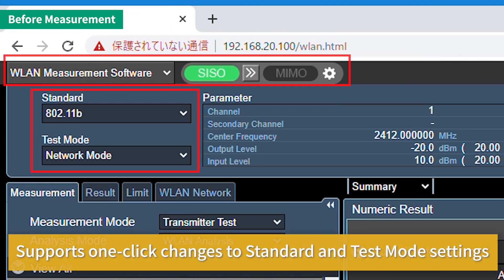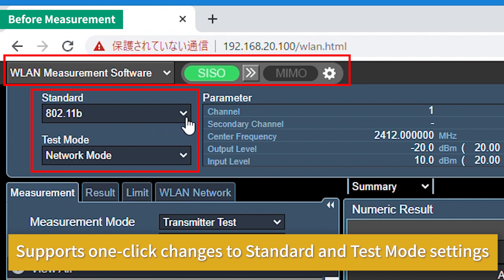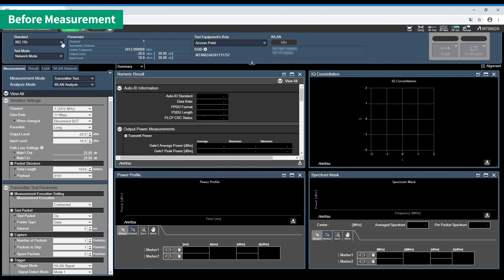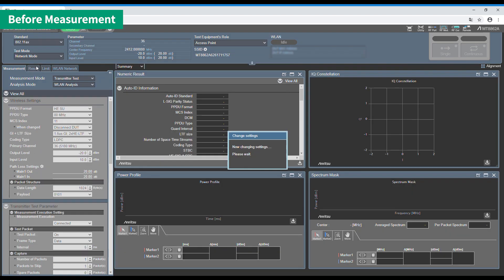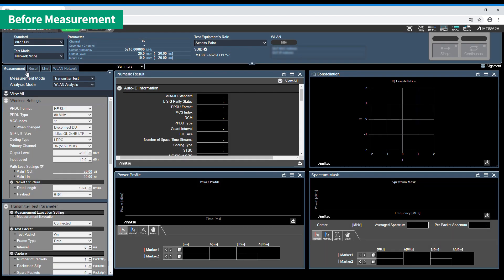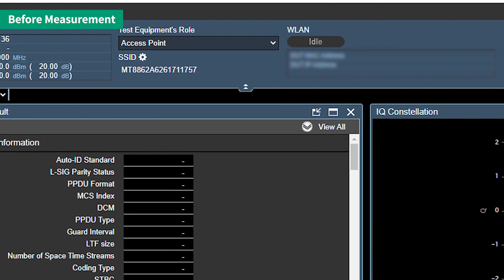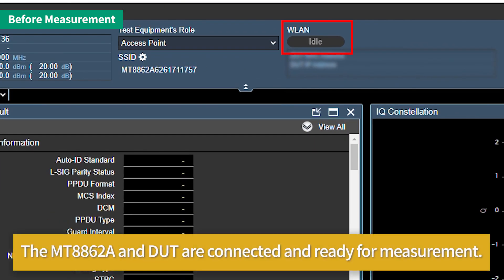Choose the standard and test mode. They can be changed by clicking with the mouse. As with a normal wireless LAN connection, the MT8862A and the DUT can be connected for measurement by choosing the MT8862A SSID from the DUT.